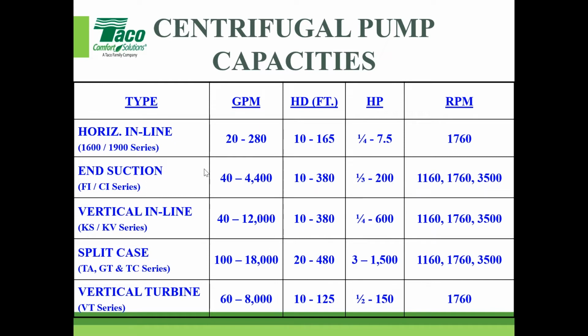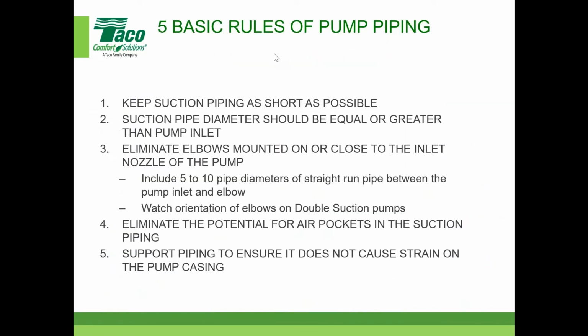We'll see. Anyways, this is a rough layout of the capacities of them as well. So a couple of other things before we finish, and I just want to go over some basic rules of pump piping. I have 5 posted here, and there are plenty of others. When you start up pumps with a drive or integral drive, it's so important to make sure the air is out of the system and the water's flowing correctly. But keep suction piping as short as possible.